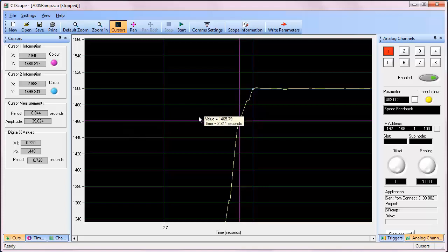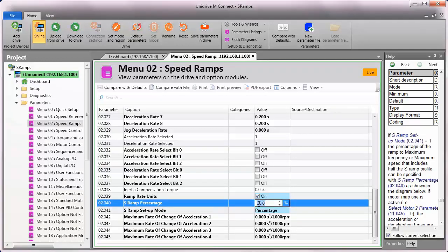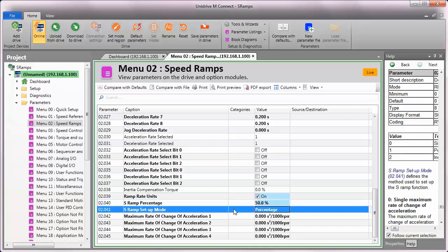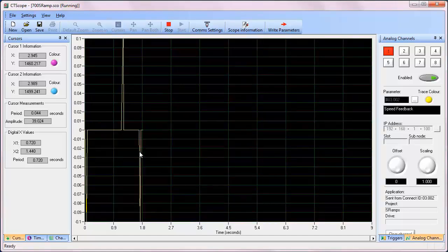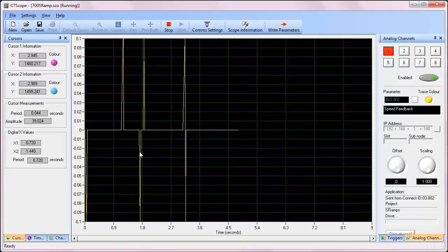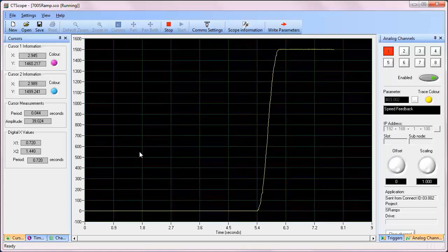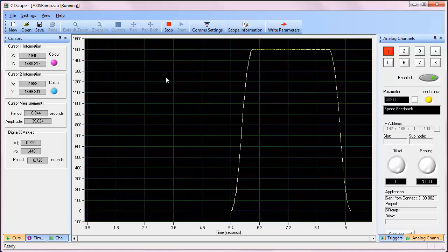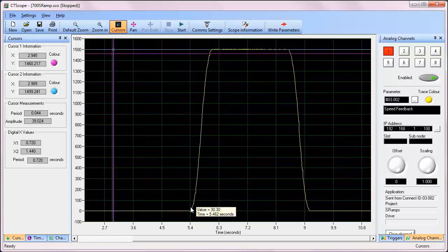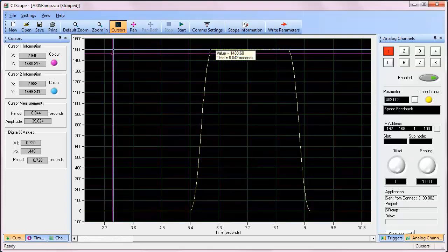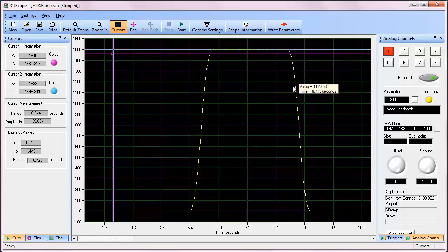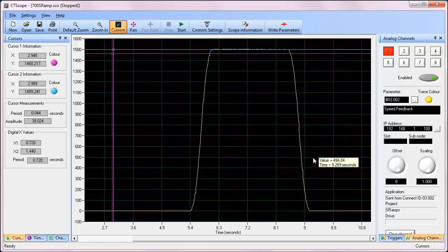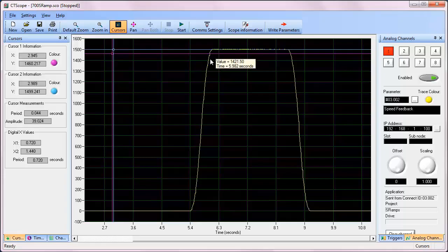Now, this parameter has a maximum as well. So in this mode, I can only set S ramp to 50%, that's the limit. Now, what that's going to look like is that's going to use half of my accel ramp and half of the decel ramp to form the S. So as you can kind of see here, in 50%, it comes up and then it immediately starts the S. So the entire shape of the accel and decel is now an S as opposed to the percent in the beginning and the end of our transitions.